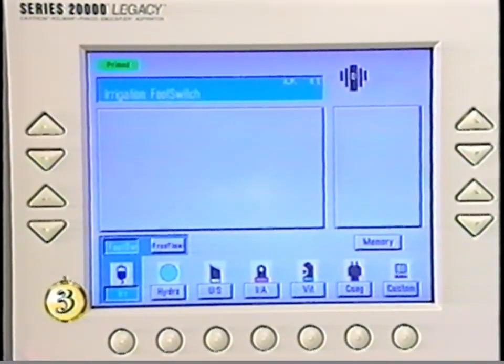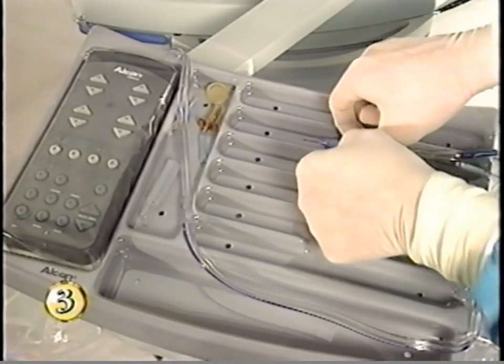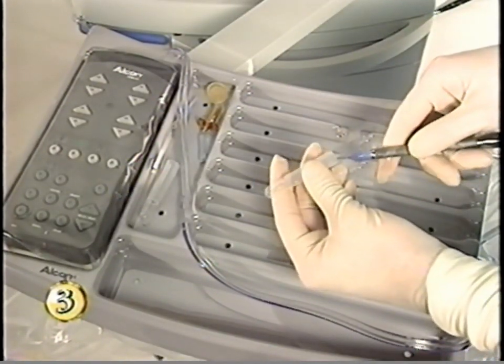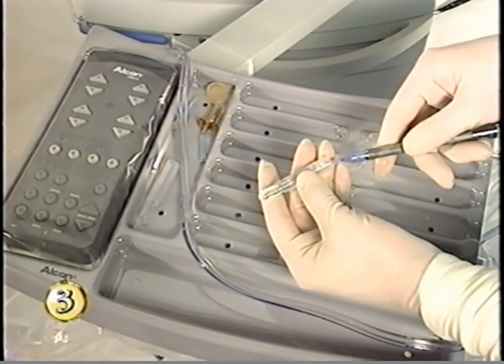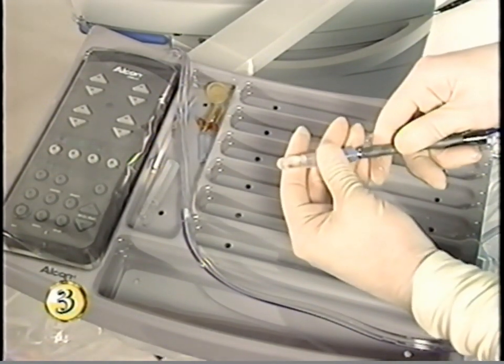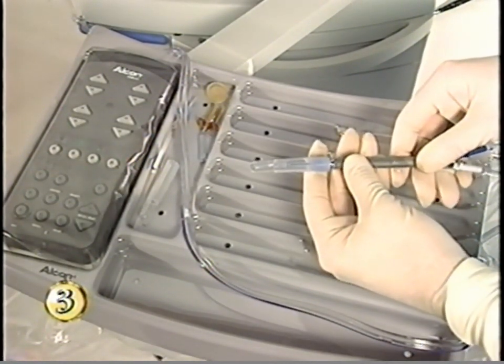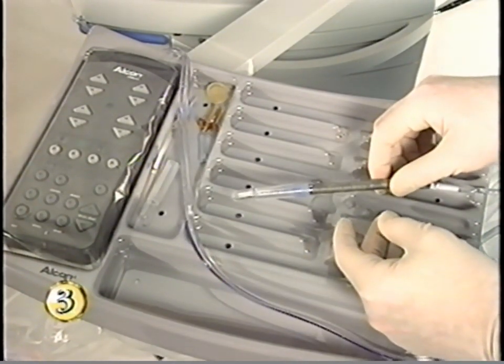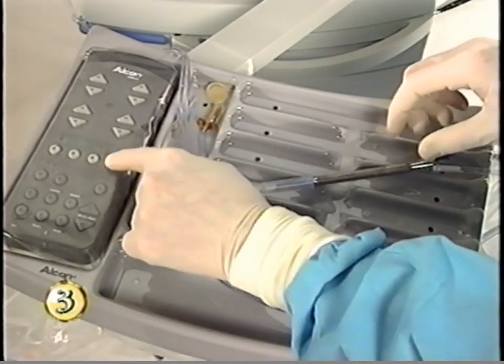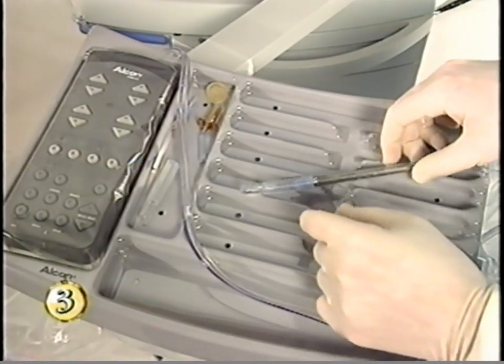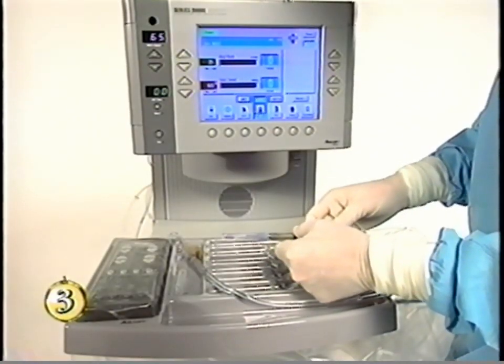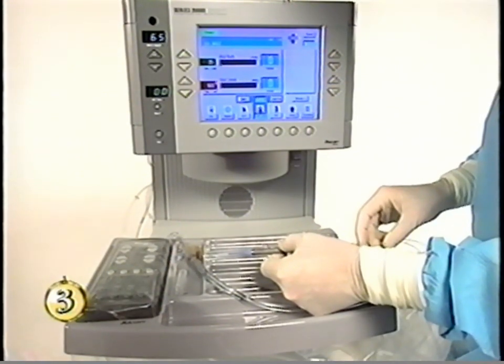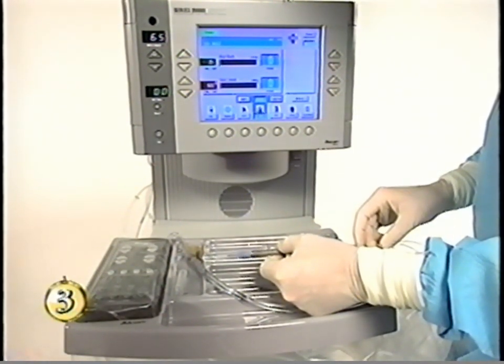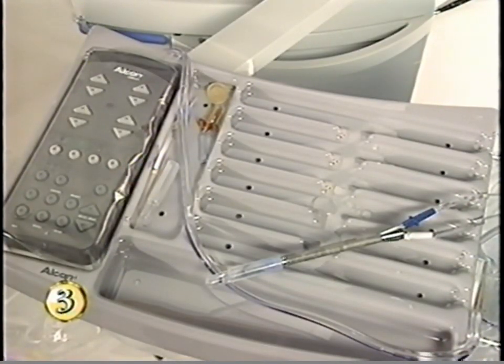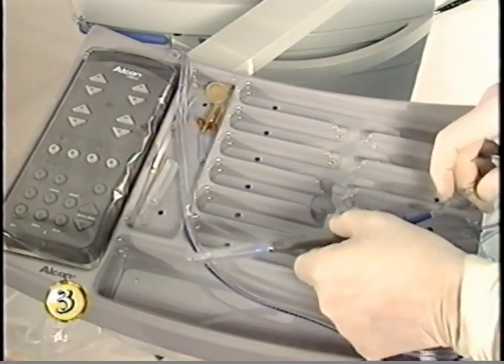Select Irrigation Foot Switch mode. Depress the foot switch until irrigation fluid streams from the sleeve. Slide a test chamber filled with BSS or BSS Plus solution onto the tip end of the handpiece and release the foot switch. Press the IA Max Mode selection key and hold the handpiece horizontally at cassette level or place it in the instrument tray. Next, perform a fluidics balance test to confirm the integrity of the tip and handpiece.